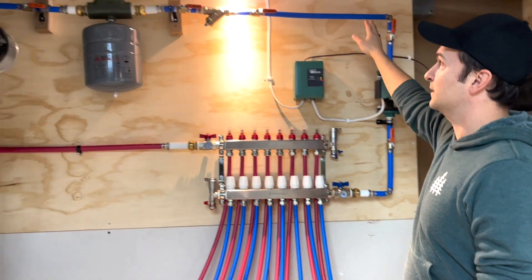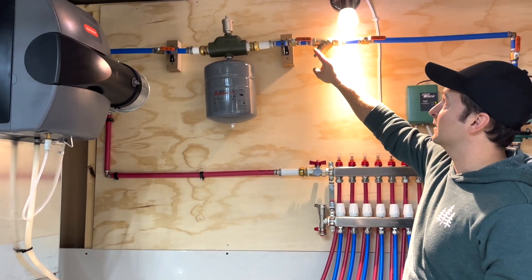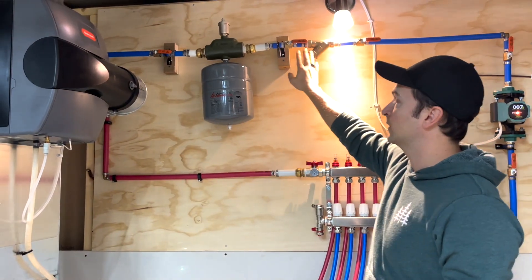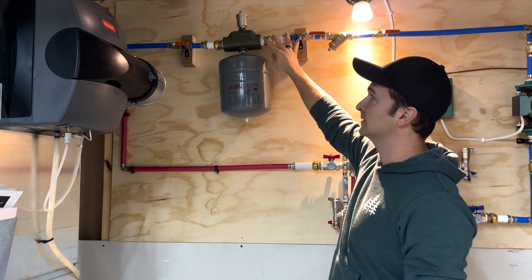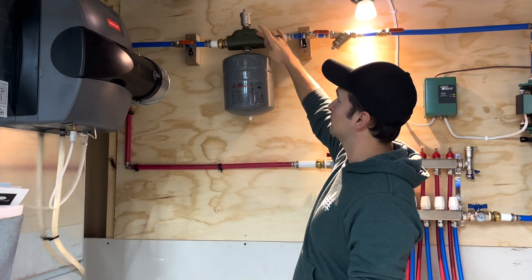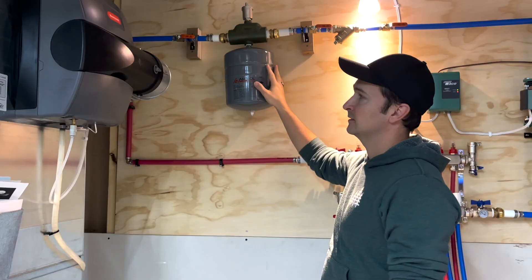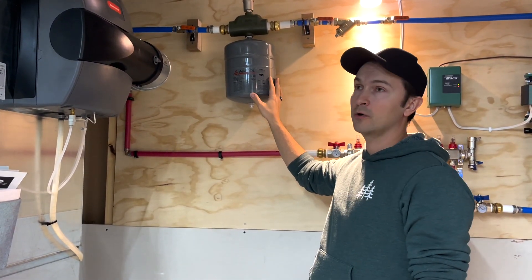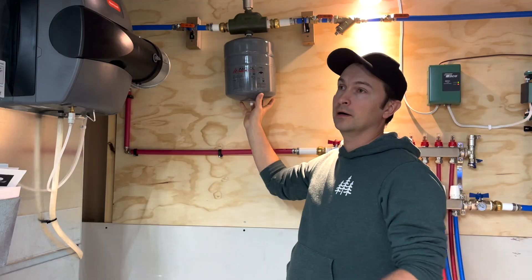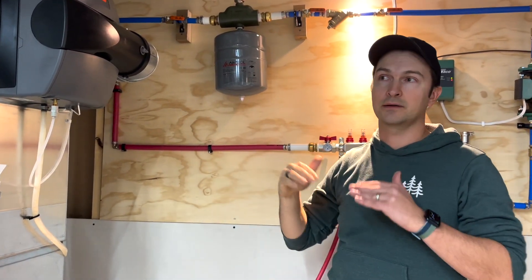The water continues here. We have a Y strainer just in case there's any debris — the debris gets accumulated here. Then we continue further into this air scoop. So if there's any air in the system, the air rises up and is evacuated by this valve. And this is the expansion tank — so if there's too much pressure from the hot water in the pipes, the expansion tank helps to relieve the pressure.